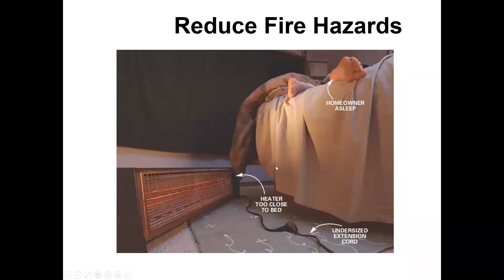A heater too close to bed material caused this fire shown here. The cord is a zip cord — an ungrounded two-wire lightweight cord, not worth much. Never put an electrical cord under a rug because doing so increases heat, and eventually the cord will catch fire.